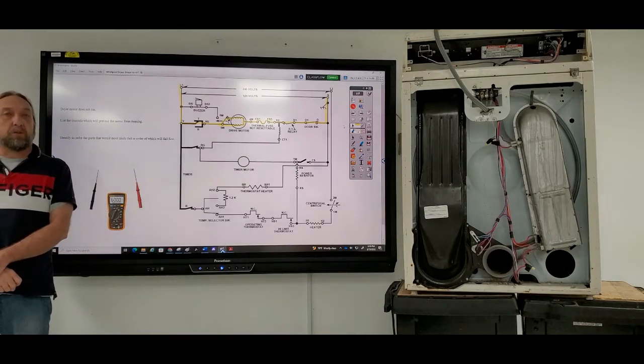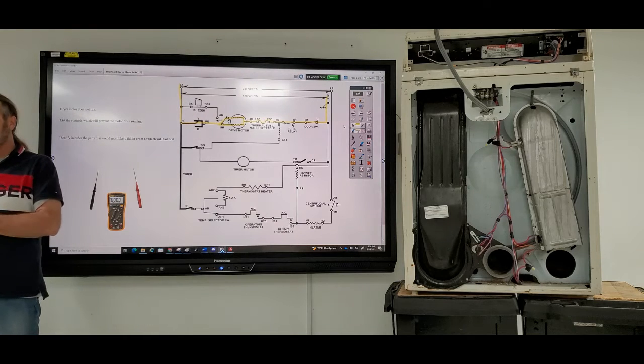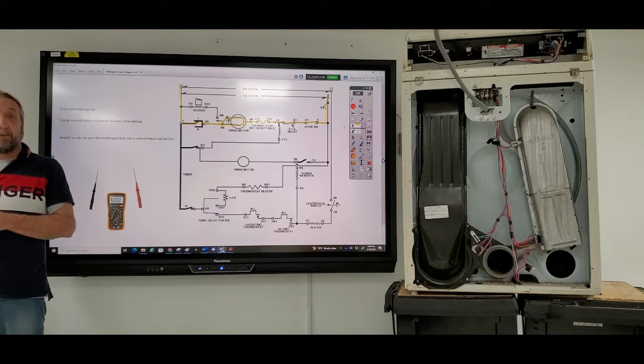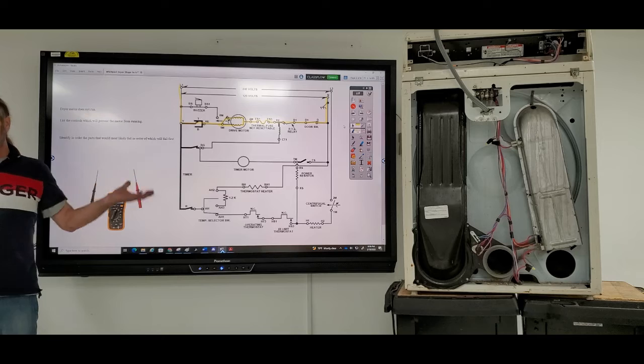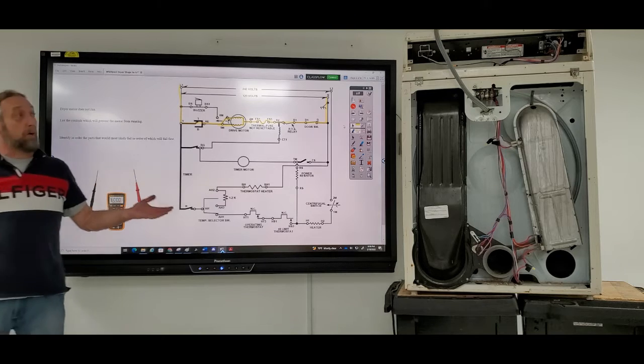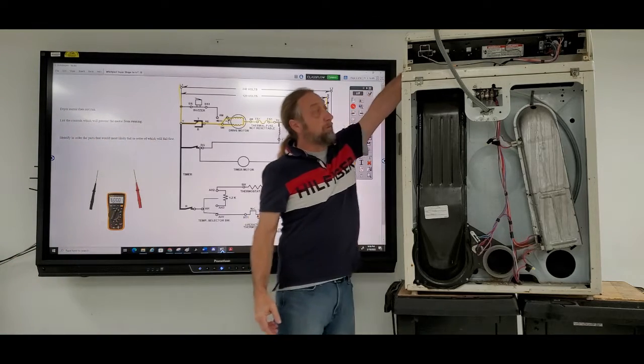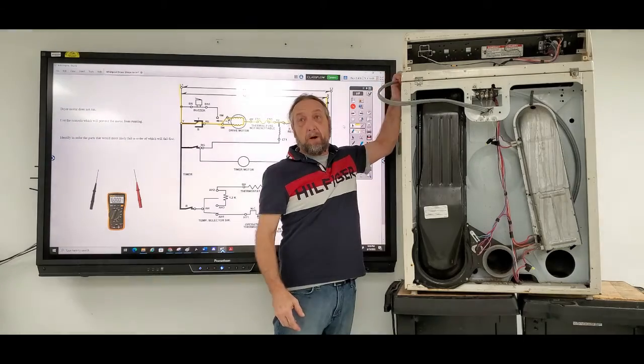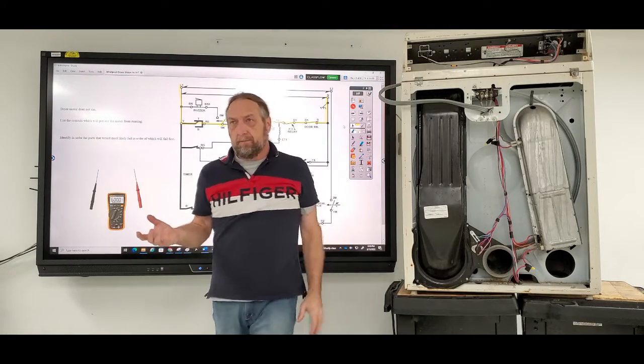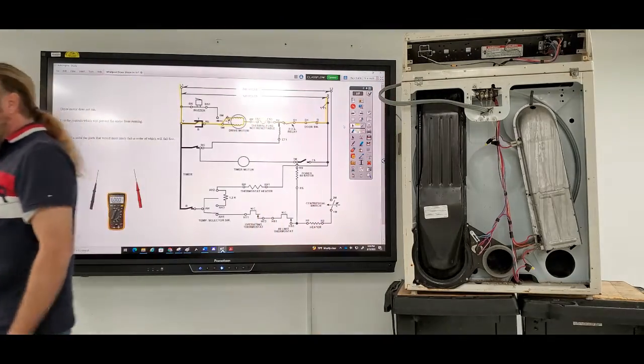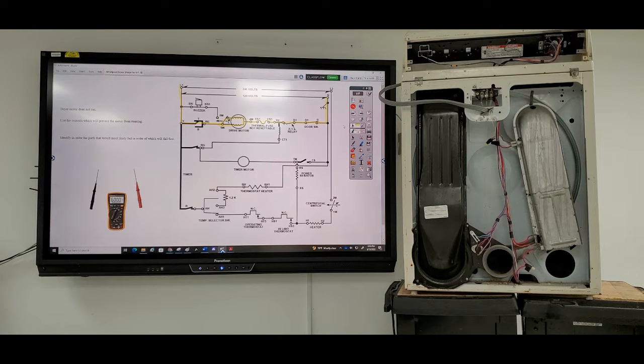How much voltage does the motor get — 120, 240, how much does it get? 120. Now this dryer does get 240 — it's got one of these 240-volt plugs on it. But 240 is really for what? The heating element. So we really don't need the 240 to get it to work, we only need 120 volts. But it's important to know that only two of those wires give us 120 for the motor, but we can get 120 from the other wires too.